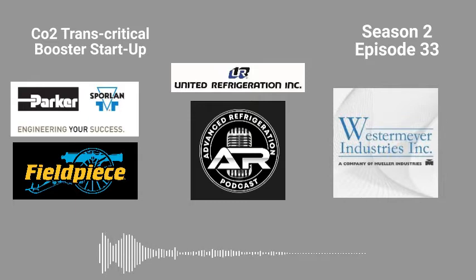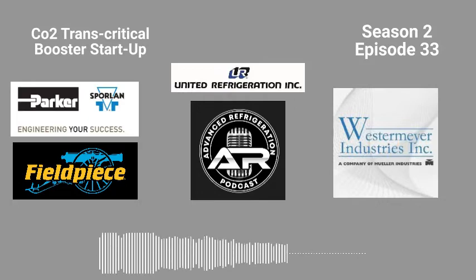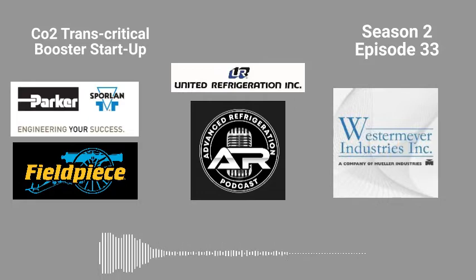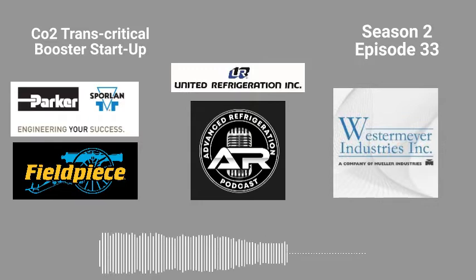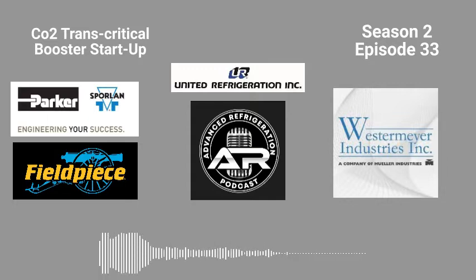Yeah, so that's become a little bit of a pain. Hopefully as all these case manufacturers catch up, they're all going to be the same version. But those are a lot easier to test because you could just hook right up to the Tech Check app and easily check that case real quick. Look at it, see the discharge error, see everything else, test the pulse valve, test the EEV, you test it all. So the biggest thing, if you got EEVs, make sure the Sporlans with that new collar.